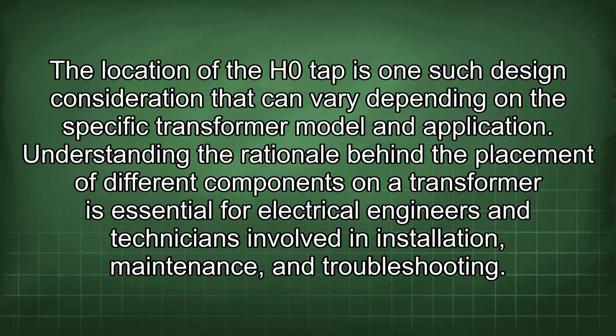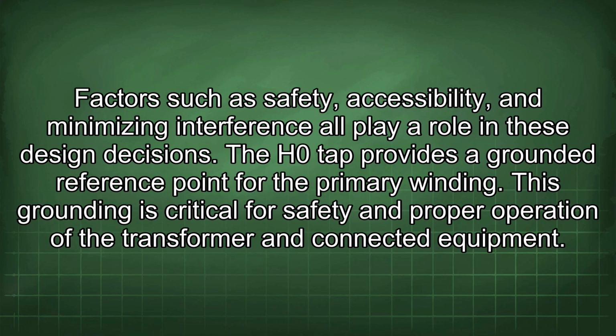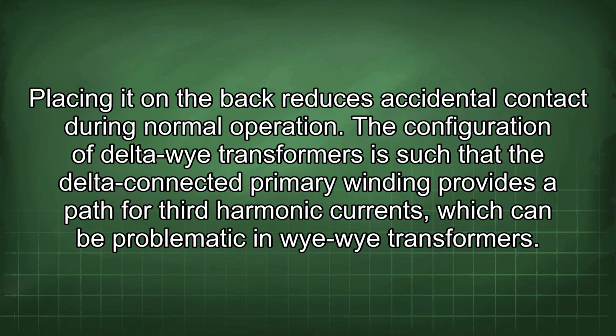Understanding the rationale behind the placement of different components on a transformer is essential for electrical engineers and technicians involved in installation, maintenance, and troubleshooting. Factors such as safety, accessibility, and minimizing interference all play a role in these design decisions. The H0 tap provides a grounded reference point for the primary winding. This grounding is critical for safety and proper operation of the transformer and connected equipment. Placing it on the back reduces accidental contact during normal operation.